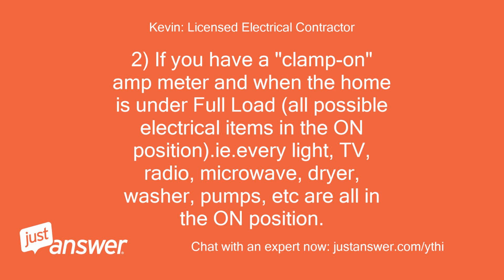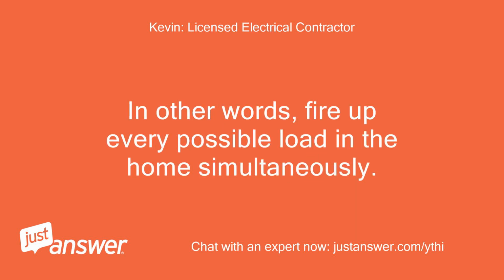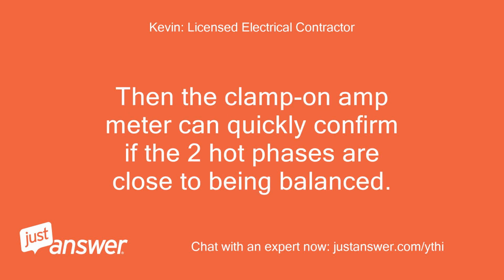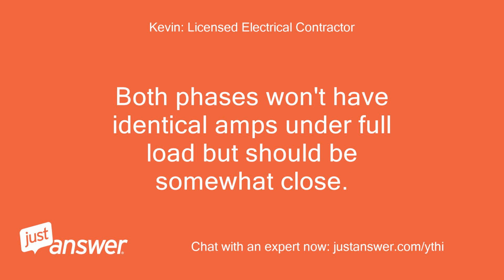2. If you have a clamp on amp meter, and when the home is under full load, all possible electrical items in the on position, every light, TV, radio, microwave, dryer, washer, pumps, etc. are all in the on position. In other words, fire up every possible load in the home simultaneously. Then the clamp on amp meter can quickly confirm if the two hot phases are close to being balanced. Both phases won't have identical amps under full load but should be somewhat close.